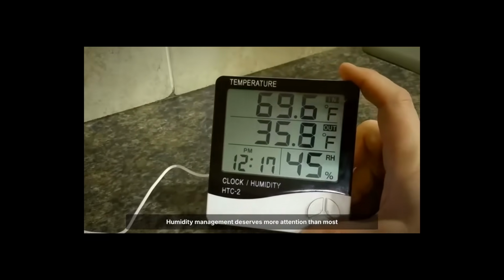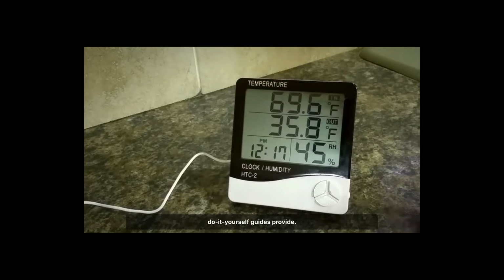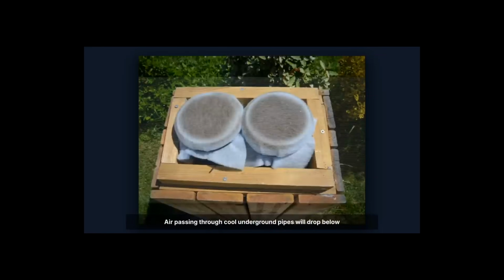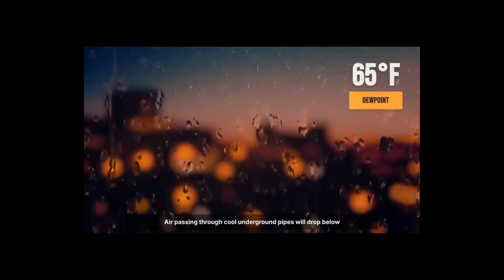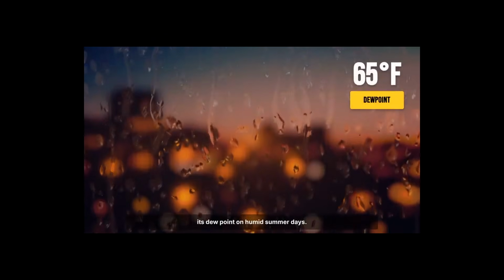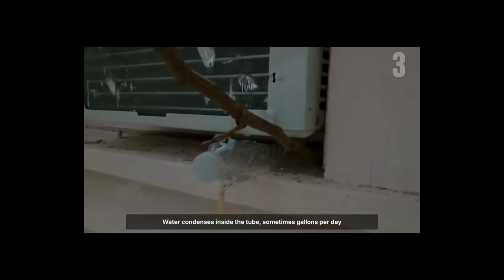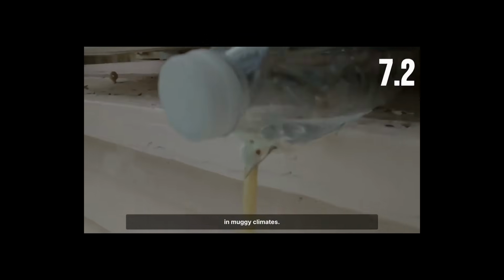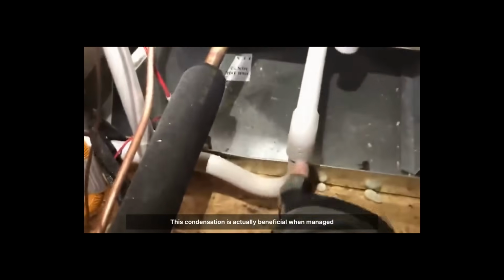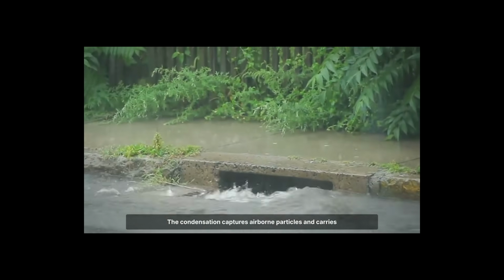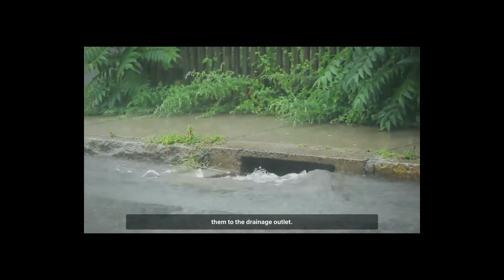Humidity management deserves more attention than most do-it-yourself guides provide. Air passing through cool underground pipes will drop below its dew point on humid summer days. Water condenses inside the tube, sometimes gallons per day in muggy climates. This condensation is actually beneficial when managed correctly. The condensation captures airborne particles and carries them to the drainage outlet.